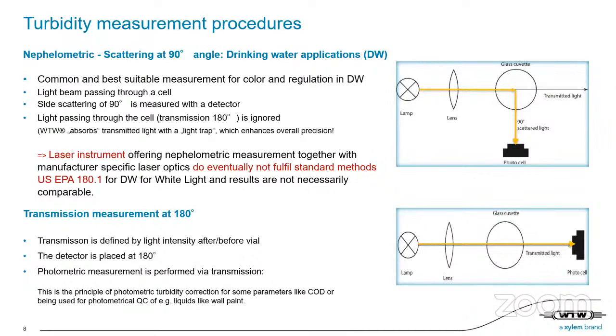Now, there are different turbidity measurement procedures. If you look here, this is our nephelometric measurement, which is used almost everywhere in the world, or I think everywhere in the world. It is the 90-degree detection of scattered light. So there is a particle which scatters the light in different directions, and our photocell is at a 90-degree angle. The light beam passes through, and this is the only angle. Laser instruments, by the way, do not always offer the same full, correct, complete optical systems. They have 90 degrees in nephelometric, but the light source is different. And this is what we will see next.